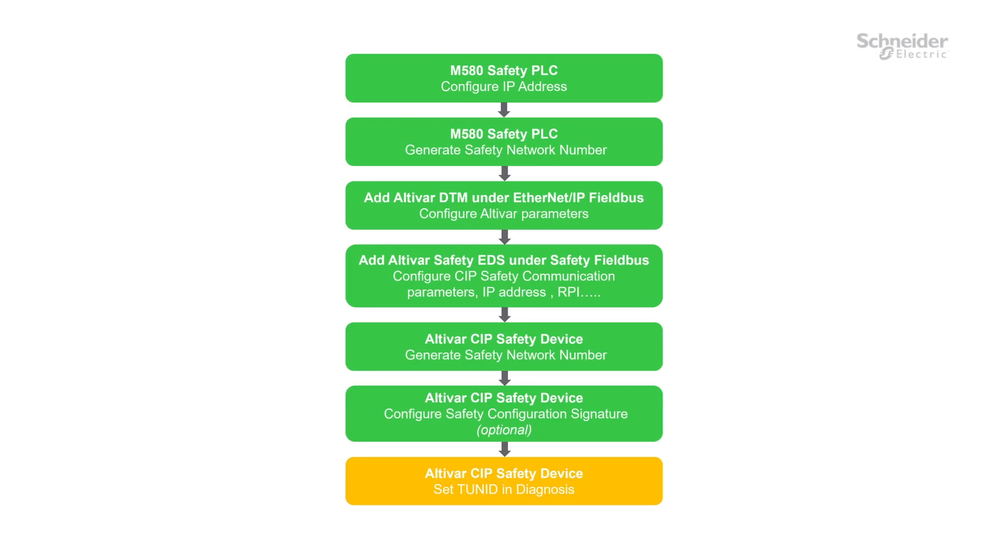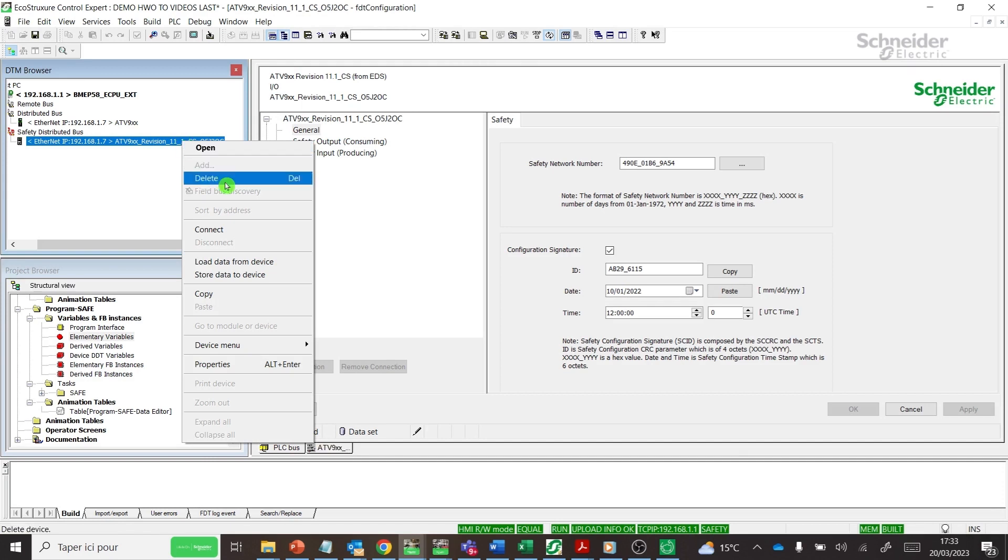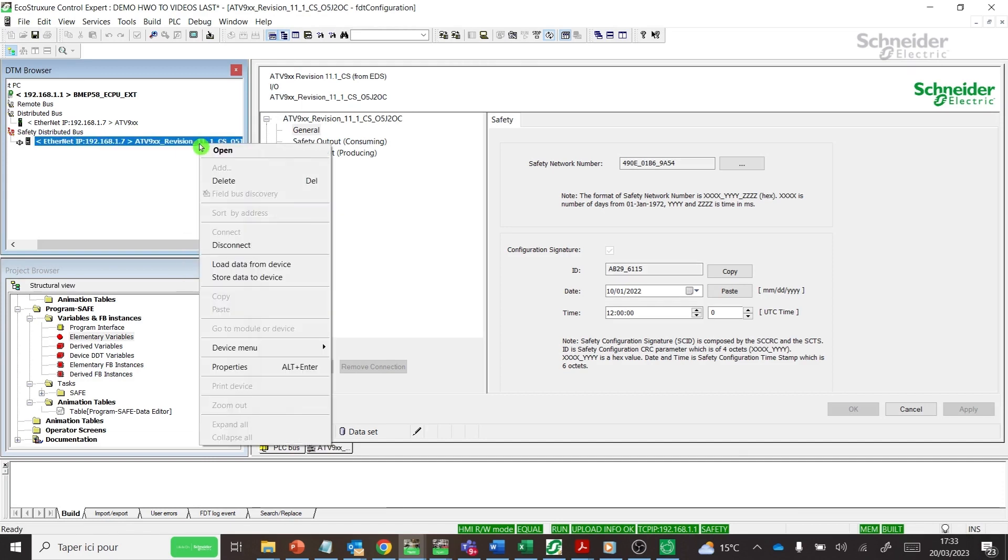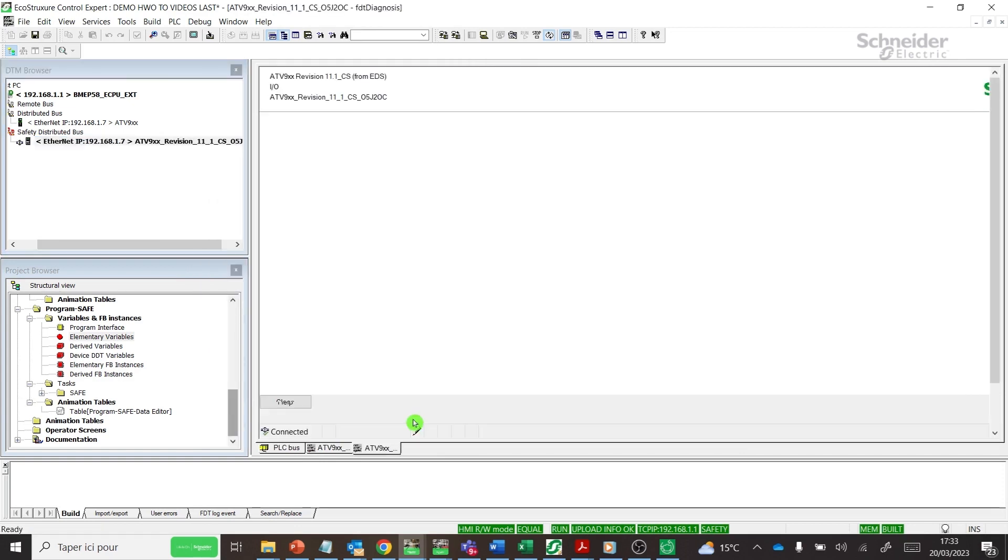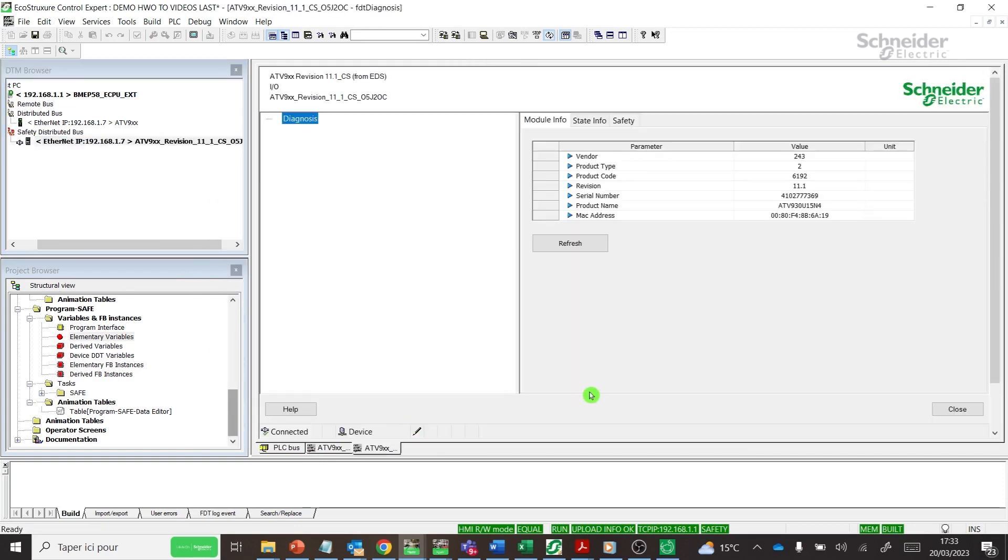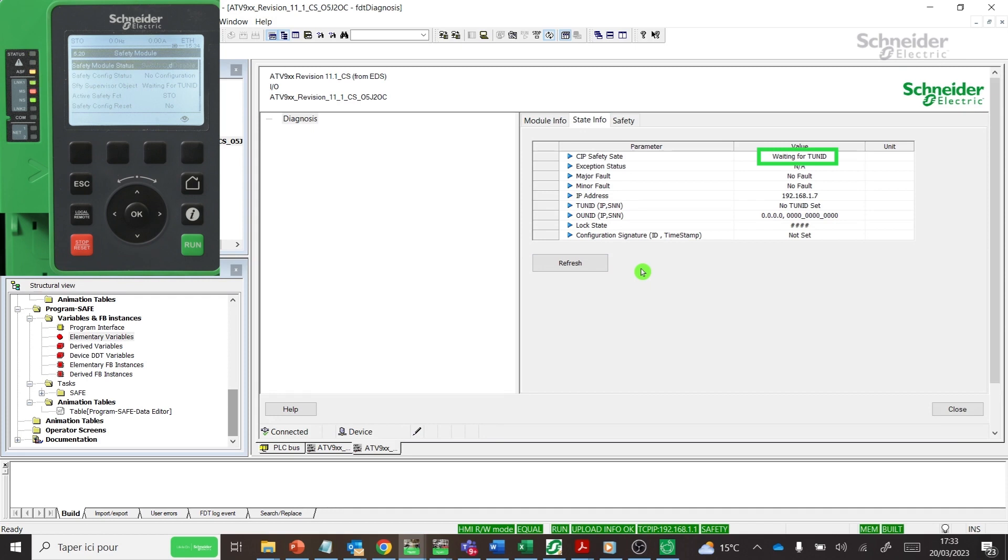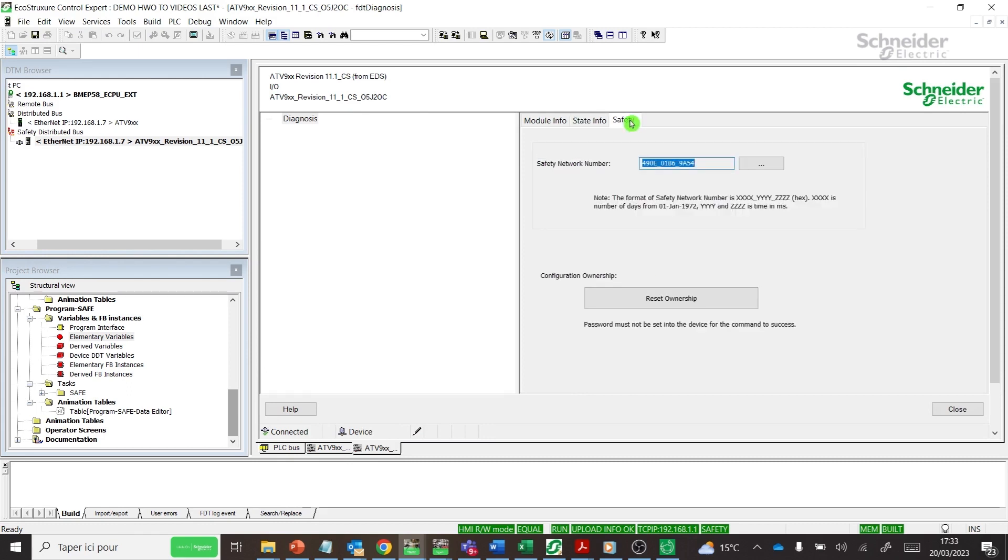Step 7: Set TUN ID for Altivar CIP Safety Device. Compile, build the project, and transfer the project to M580 Safety PLC. Connect Online with Safety EDS. Go to Device Diagnosis menu. The CIP Safety Module is not configured yet. Module Safety, MS, LED flashes red, then green. Go to the Safety tab. Set TUN ID to Drive.